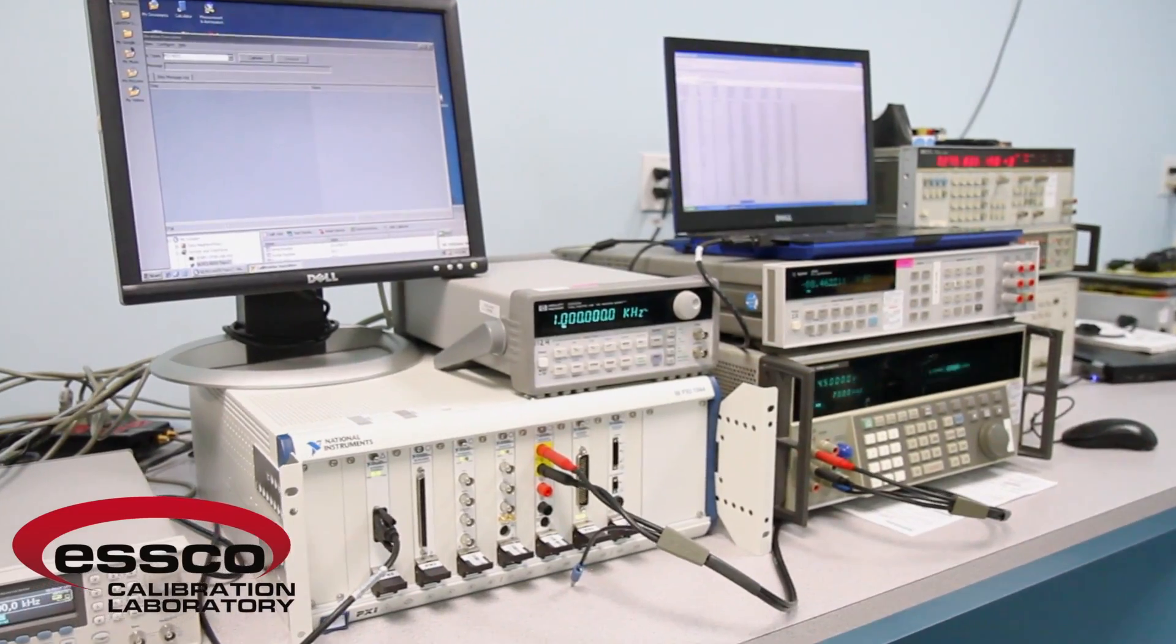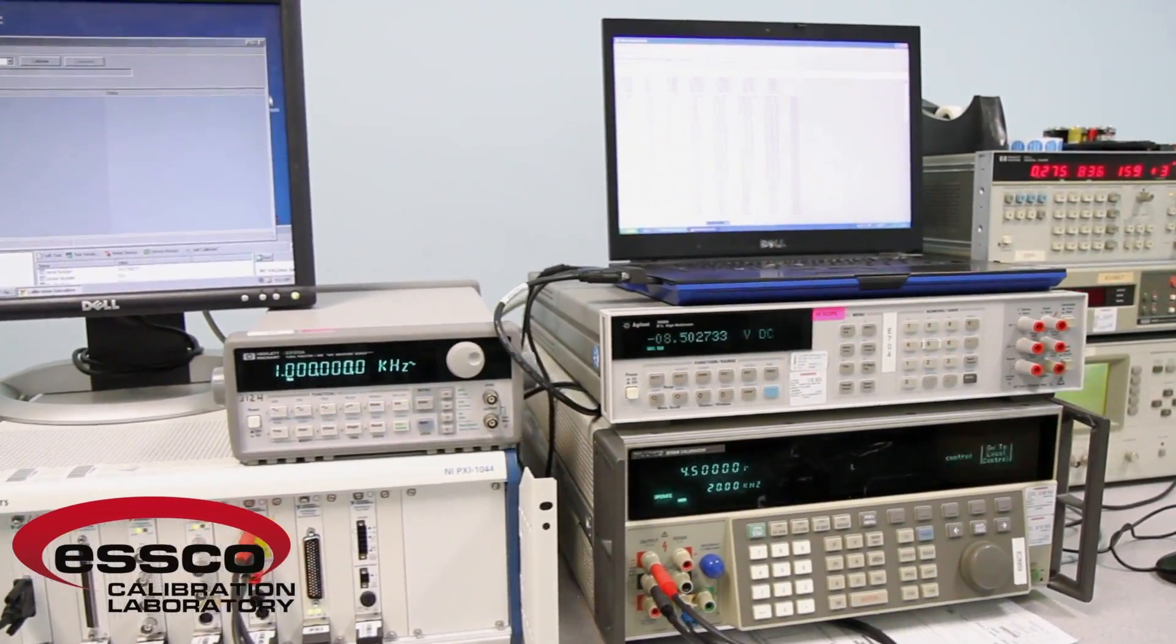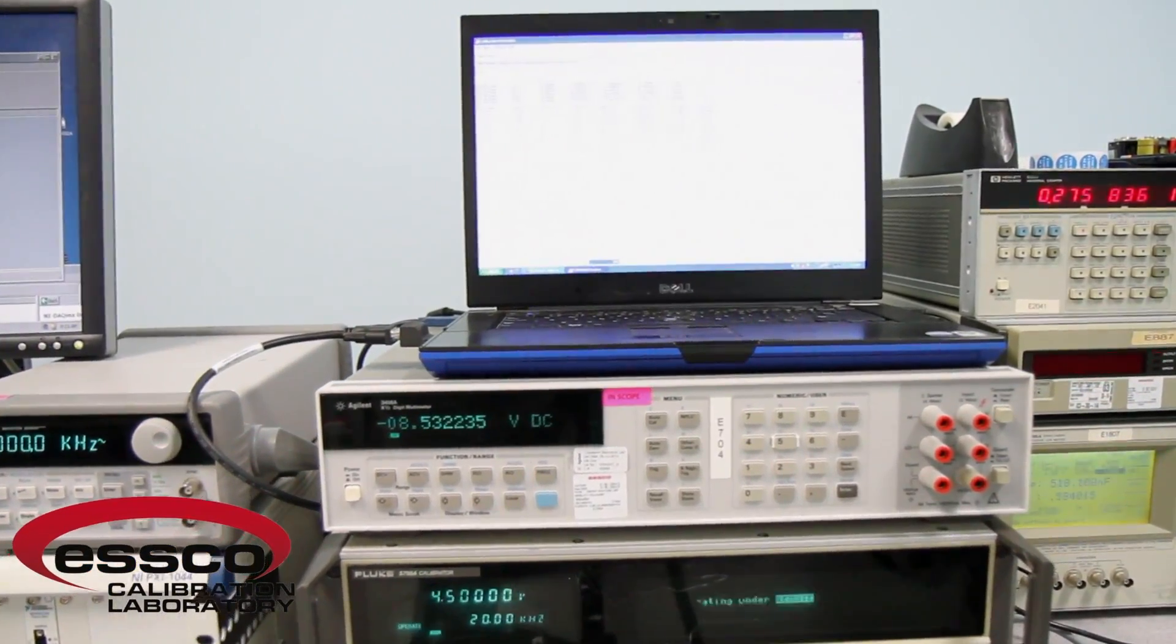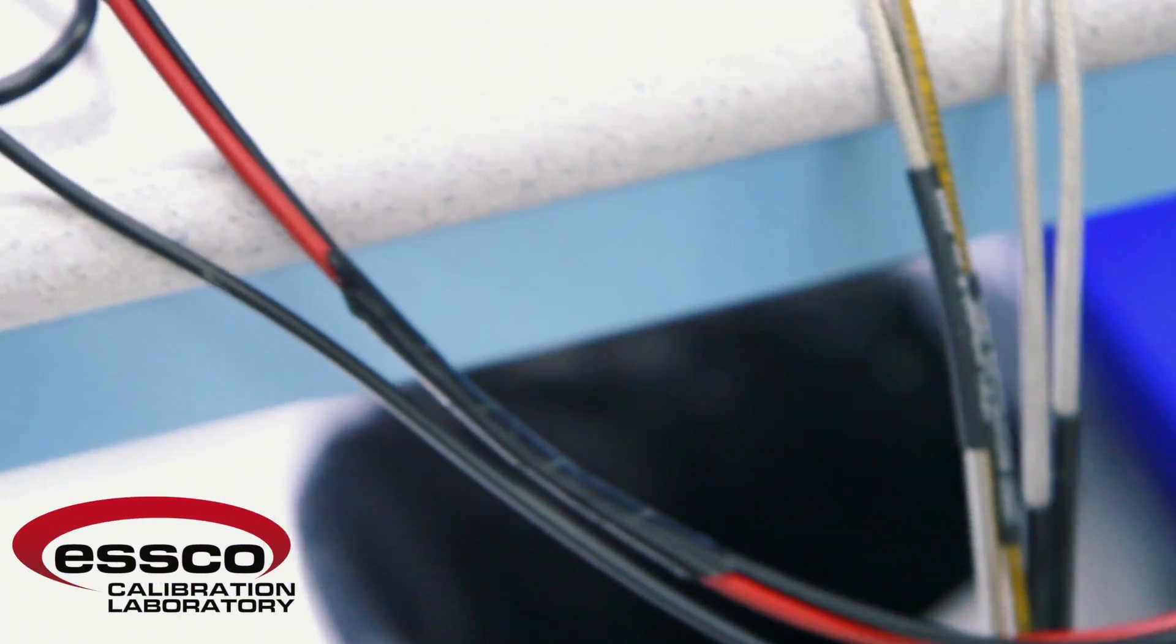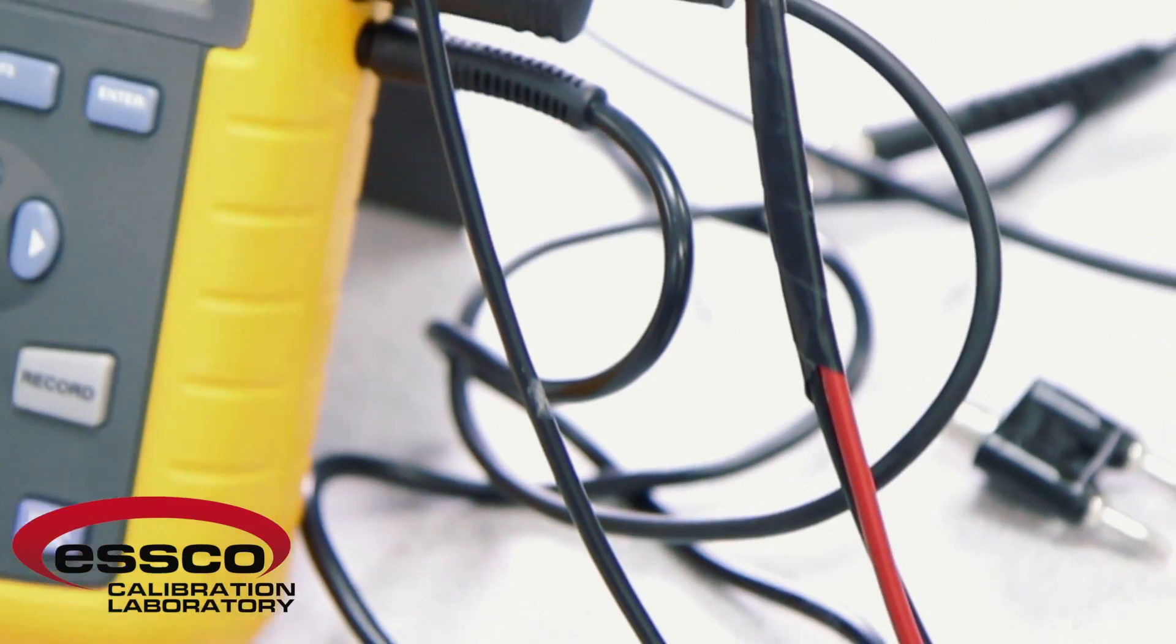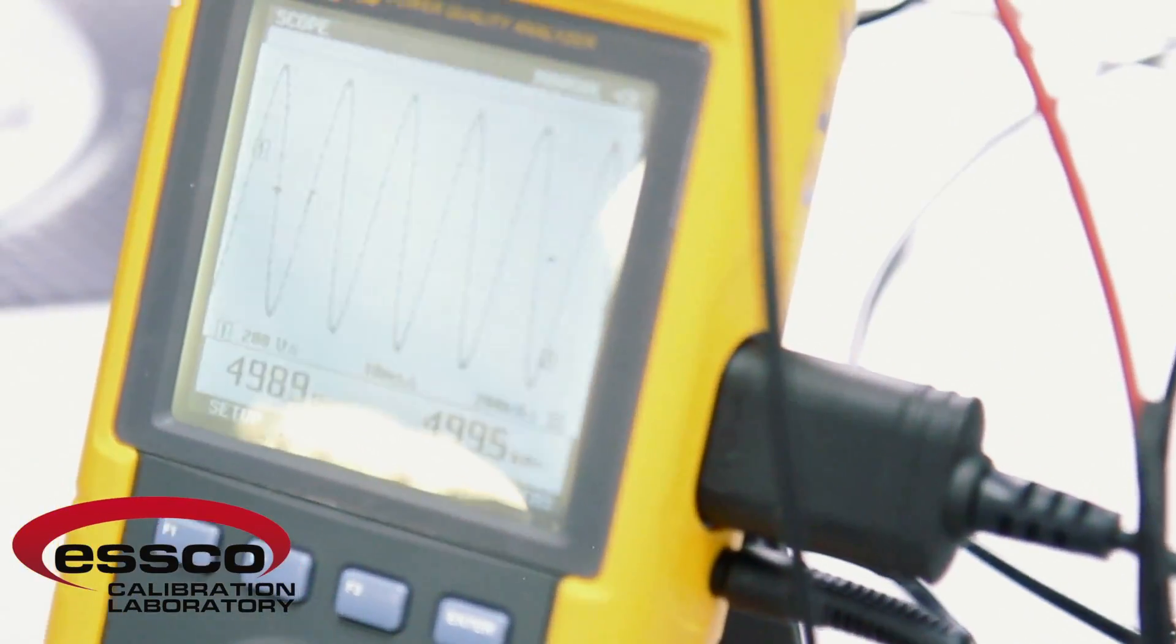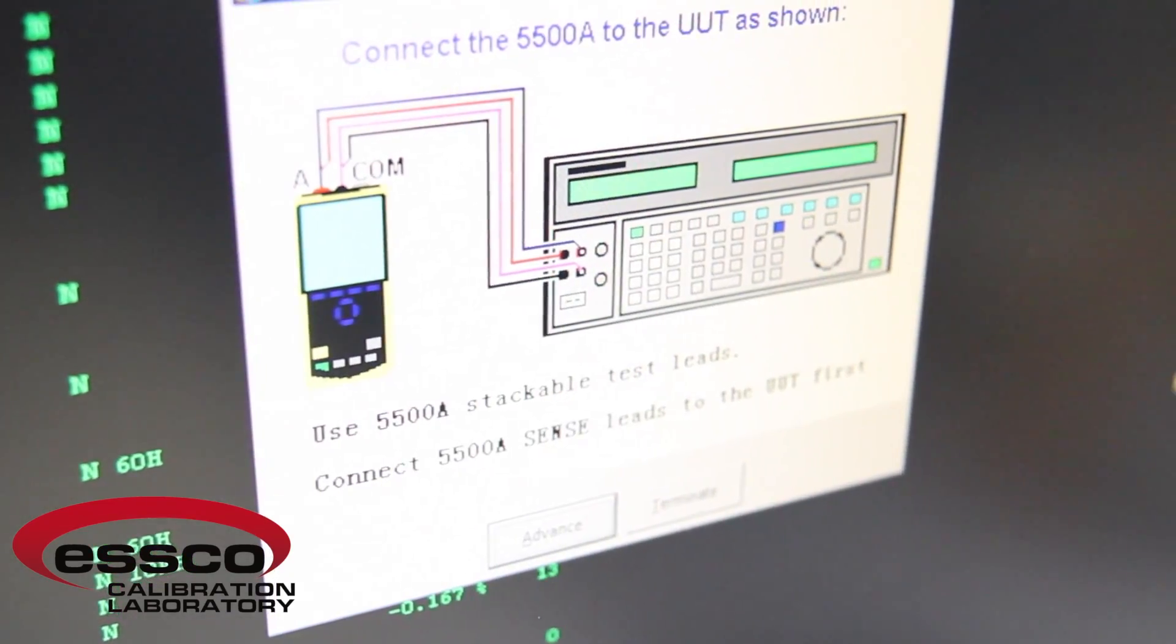After the calibration has been completed, a report documenting your calibration and adjustment results is provided. For other electronic equipment calibrated in our lab, such as high-accuracy DMMs, oscilloscopes, and multifunction calibrators, we use the Fluke MetCal program.